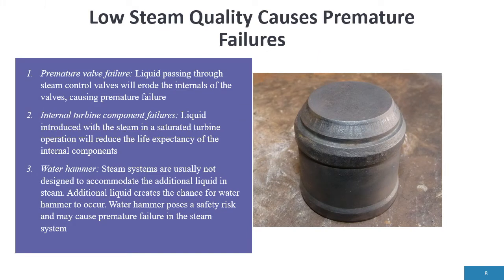Low steam quality can cause premature failures in components — it happens all the time. Premature valve failure occurs because condensate passing through a valve will tear the valve internals apart. As you can see on the right-hand side, the erosion of the valve is from condensate passing through. Internal turbine component failures are also a detriment — condensate passing through a saturated or superheated steam turbine is harmful. Additionally, if steam quality is very poor, the additional condensate can build up and cause water hammer. It has a negative effect throughout the system, and that's one of the key reasons we need to be monitoring steam quality.